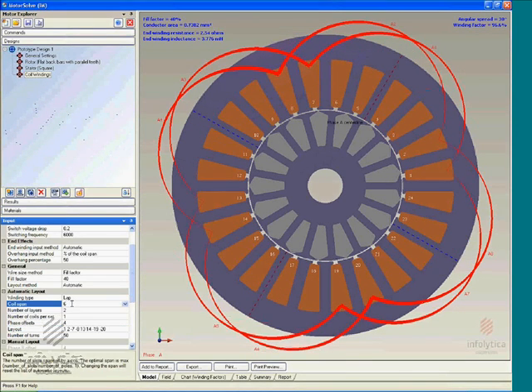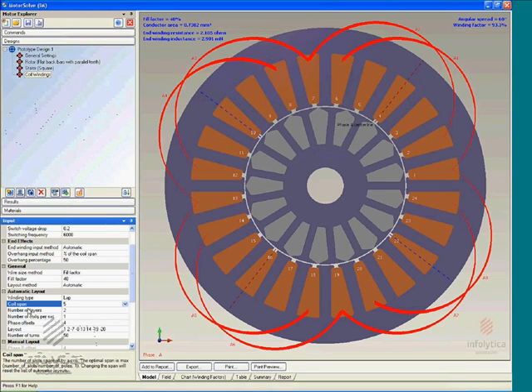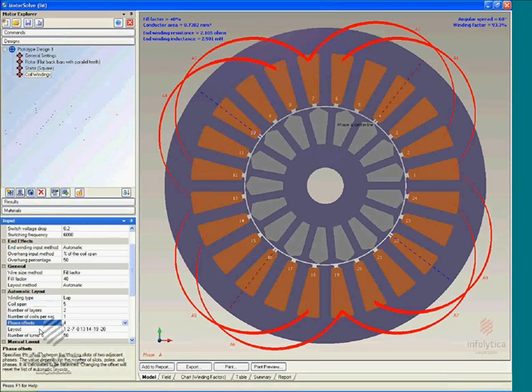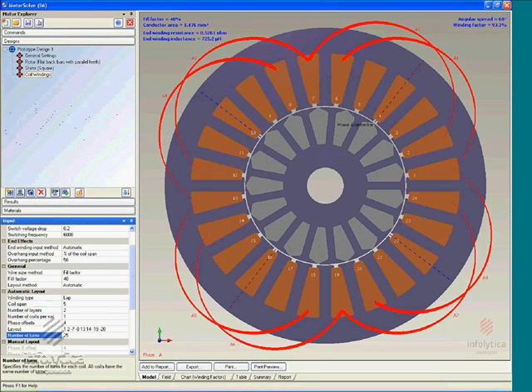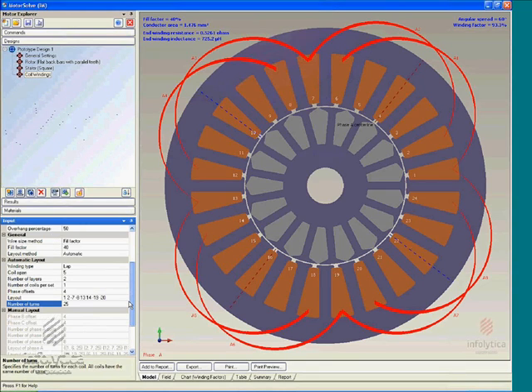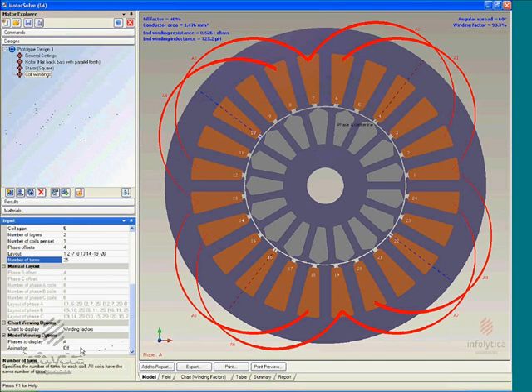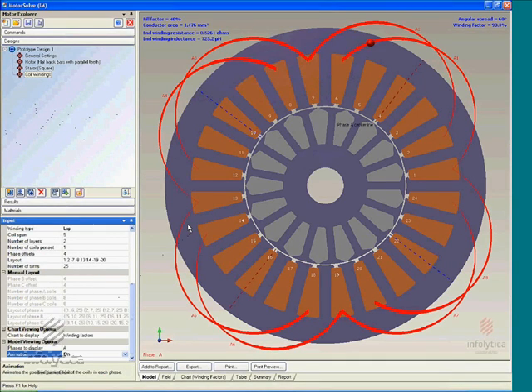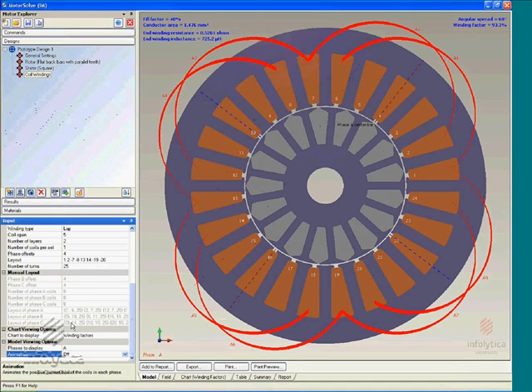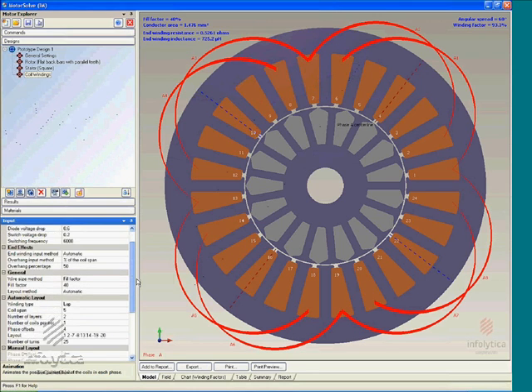A number of factors could potentially affect the list of balanced winding configurations, including the coil span, the number of layers, the number of coils per set, phase offset, et cetera, as well as specifying a number of turns that the user has control over to generate this list of balanced winding configurations. It is also possible to have an animation showing the go and return sides of the coils that define a particular configuration from this list.